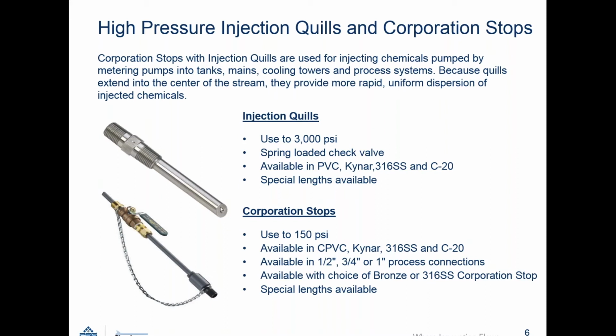They are limited at 150 psi, available in CPVC, Kynar, stainless steel, and Carpenter 20. And the size is anywhere from 1/2, 3/4, and 1 inch process connections. We also have stainless steel corporation stops, and if that's needed, bronze is standard. And we also have special lengths available.